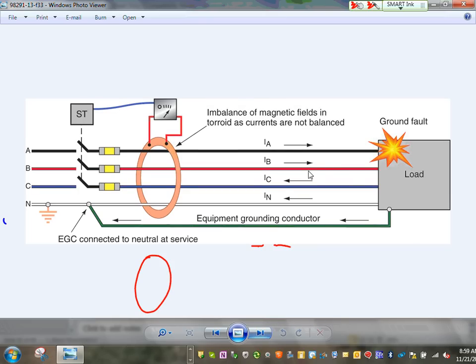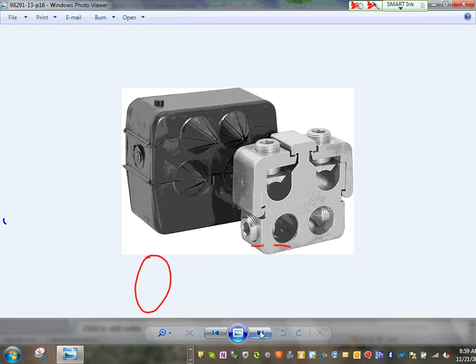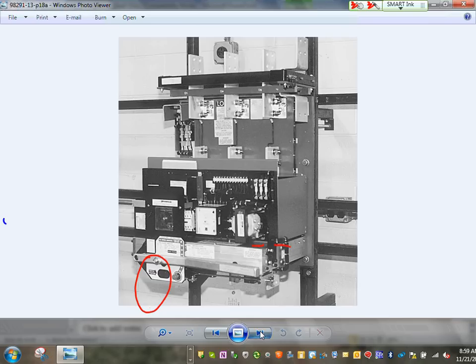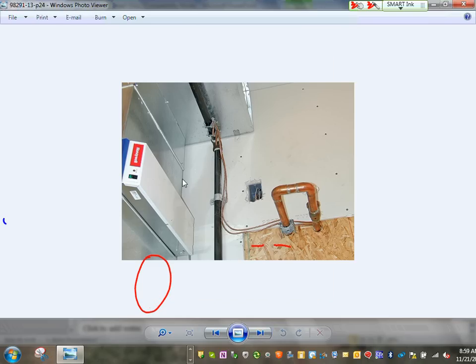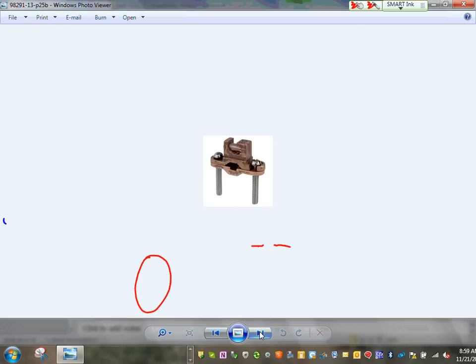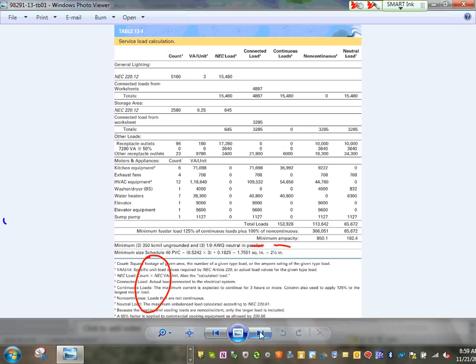So what happens, guys, if you can see, if you have a ground fault right now there will be current going right in here. So that CT will see the difference, sense the difference, send the signal to this trip unit, and it will open the circuit breaker. It will open the circuit breakers. Different connections, different bonding of the water. You can see bonding it for safety. Different hardware that you can use.